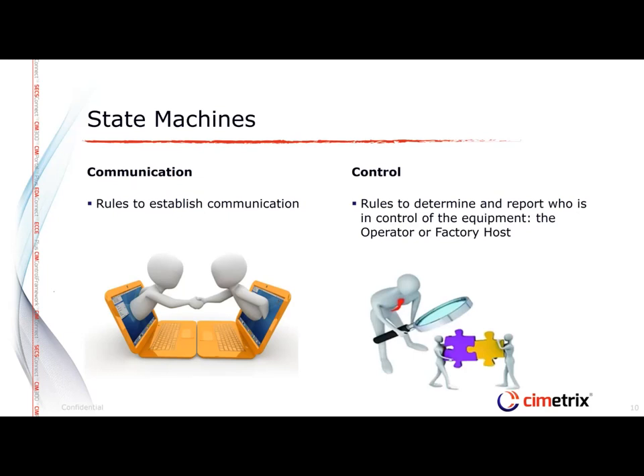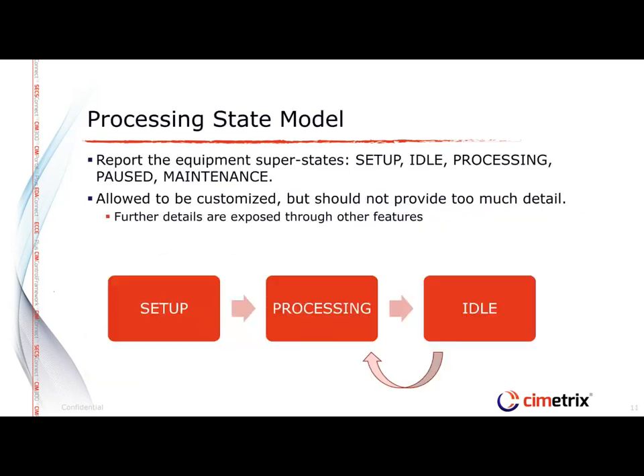GEM has state machines to manage different features. There is one for managing the rules to establish communication, and another for managing control of the equipment — because sometimes you run the equipment with the operator in charge, and sometimes you want to run it with the factory in charge through remote control. Every equipment is required to implement a processing state model, so you can monitor the basic state of the equipment — whether it's actually processing or sitting idle. You can also customize this to provide more detail.